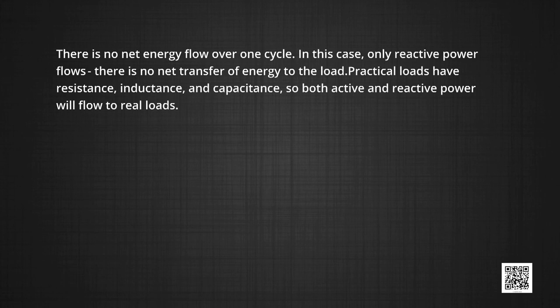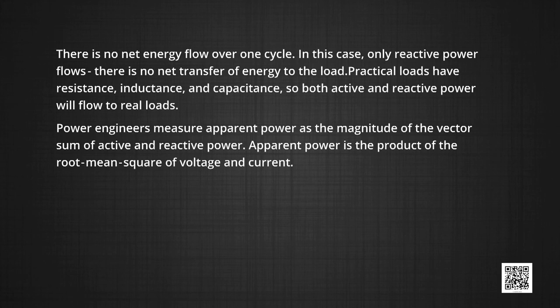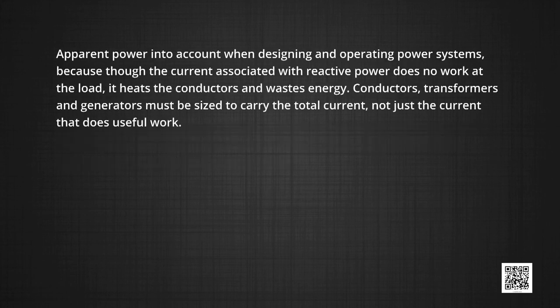Practical loads have resistance, inductance, and capacitance, so both active and reactive power will flow to real loads. Power engineers measure apparent power as the magnitude of the combination of active and reactive power. Apparent power is the product of the RMS voltage and current. Apparent power must be taken into account when designing and operating power systems, because even though the current associated with reactive power does no work at the load, it heats conductors and wastes energy. Conductors, transformers, and generators must be sized to carry the total current, not just the current that does useful work.